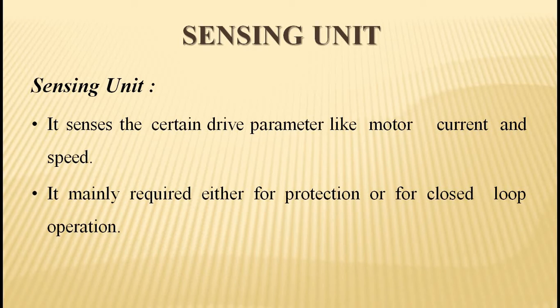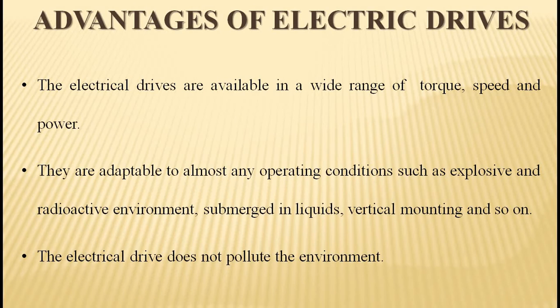The sensing unit continuously senses the output from the motor — which may be motor current or speed — and feeds it back to the control unit. The control unit then controls the output of the modulator, which in turn controls the motor. This is how closed loop operation is achieved. These are the main components used in an electric drive.